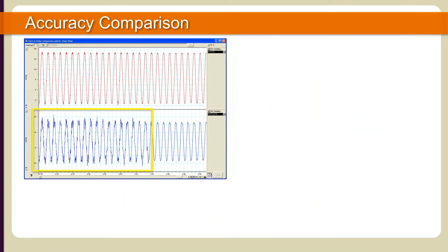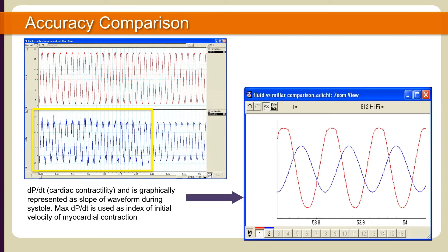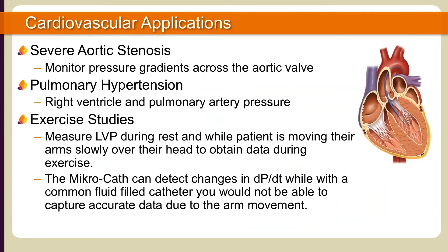In this waveform, we see the effects of tapping both a Millar high-fidelity catheter and a fluid-filled catheter. Notice the artifact collected in the blue channel, where the red high-fidelity signal is not affected by mechanical disturbances along the catheter lead. This plot shows a dP/dt waveform of both the high-fidelity catheter in red and the fluid-filled catheter in blue. The high-fidelity signal is plotted with greater accuracy — notice the time delay and dampened signal of the blue waveform.